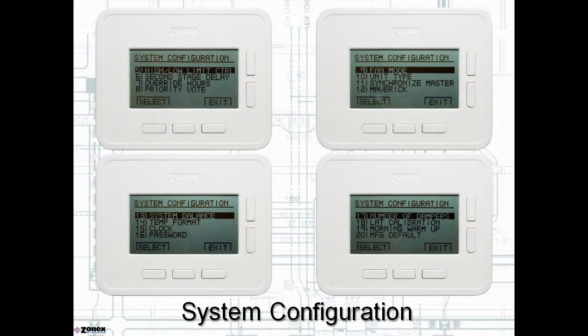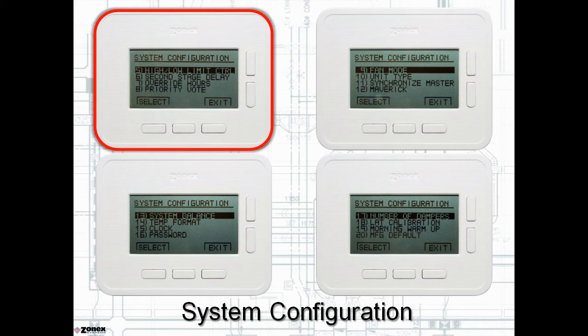Additional screens and functions accessed on the monitor thermostat include setting high and low system limits and cut in or cut out set points, delaying second stage operation, selecting override hours from 2 to 8 hours, and a priority vote option to increase weights or the importance of a thermostat in the voting process.